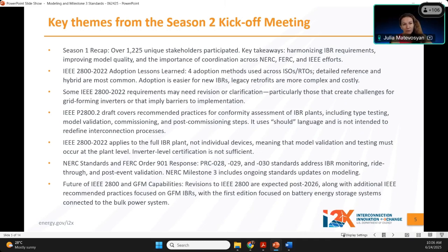We talked about the IEEE 2800.2 draft, which covers recommended practices for conformity assessments of inverter-based resource plants. The draft includes type testing, model validation, commissioning, and post-commissioning steps. It uses 'should' language, not 'shall', as IEEE 2800 does. It's not intended to redefine the interconnection process, but rather to provide guidance on recommended practices for conformity assessment with applicable interconnection requirements. IEEE 2800 applies to the full IBR plant and not individual devices, meaning that model validation and testing must occur at the plant level, in addition to inverter-level certification.